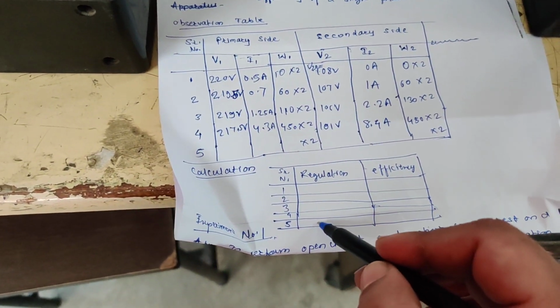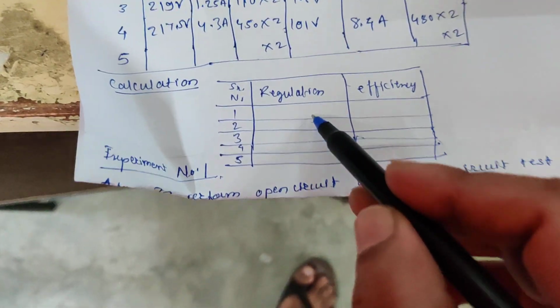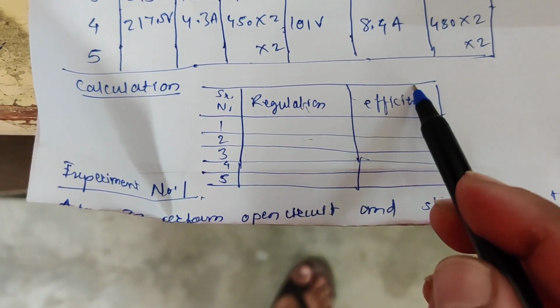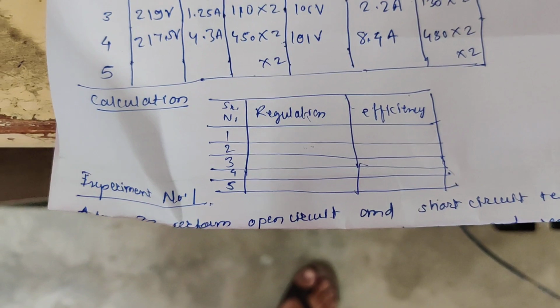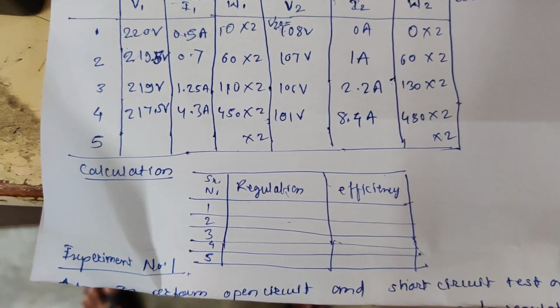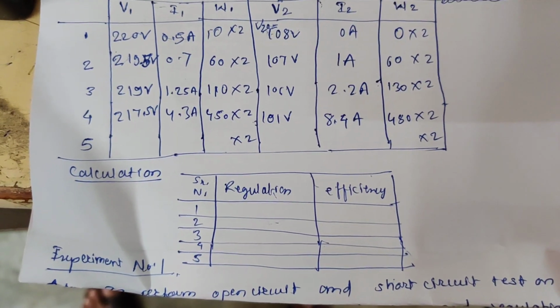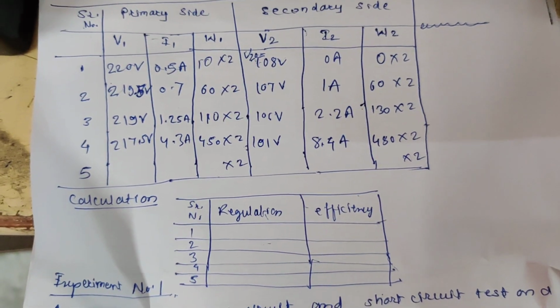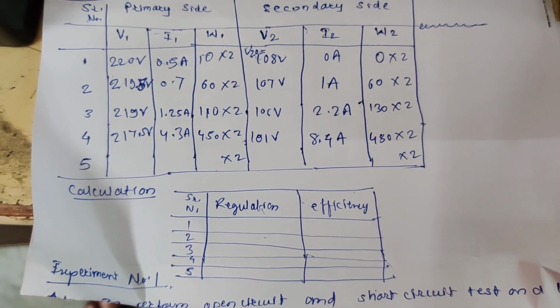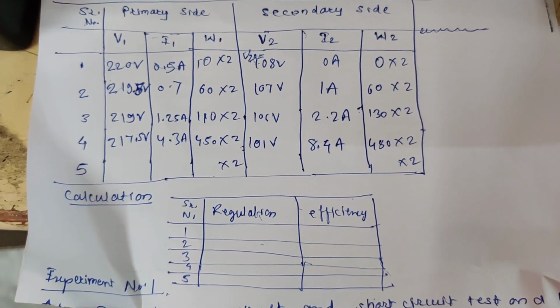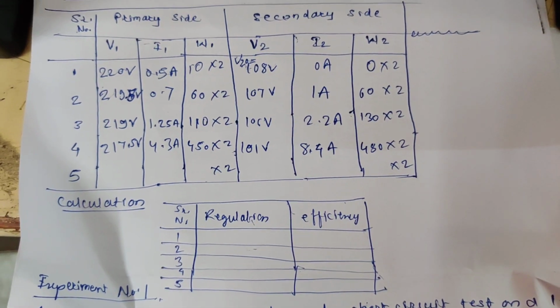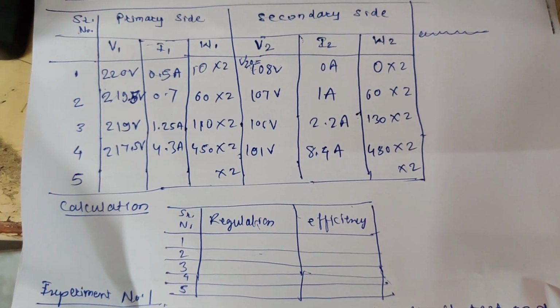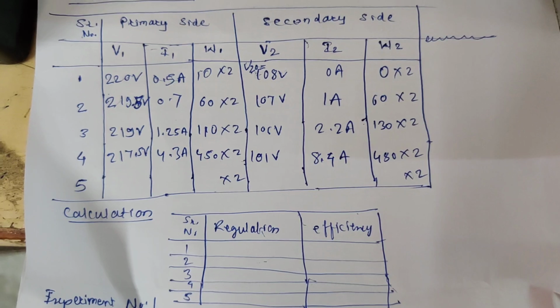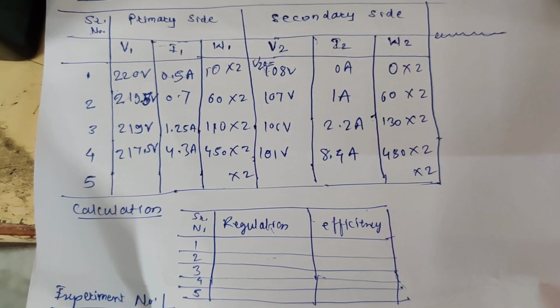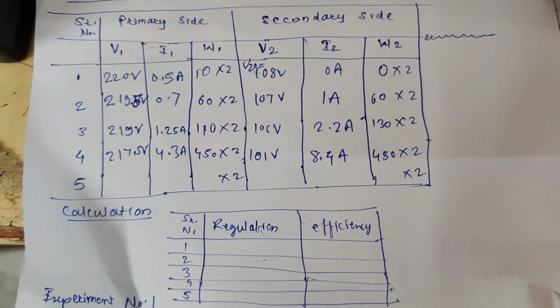So this is how I have made the table, which has two things: one is regulation and another one is efficiency. Why we calculate regulation and efficiency is, by calculating the regulation we may identify the efficiency at which your transformer is supposed to run. That is how we have to calculate the regulation. The formula for regulation is (no load voltage minus full load voltage) upon full load voltage.